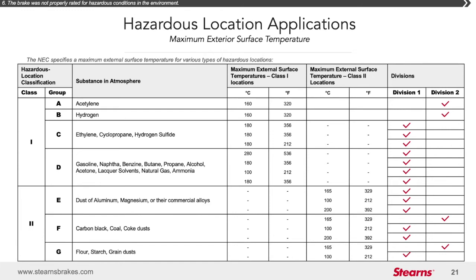Class 2 is for locations with combustible dusts. An electric disc brake for Class 2 must be enclosed to restrict the entry of ignitable dusts or exit of sparks or hot gases, which may cause the ignition of dust suspended in the air. The exterior surface temperature of the brake enclosure must be limited so that it can function at its maximum rated duty cycle without causing dehydration or carbonization of the dusts that are present.